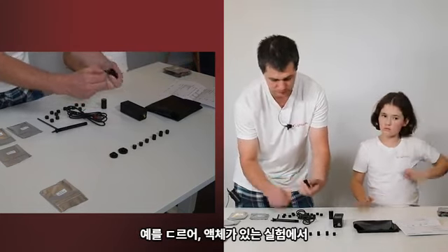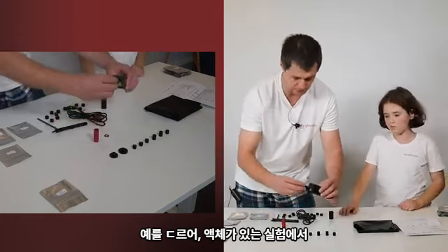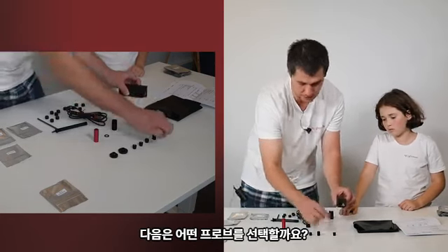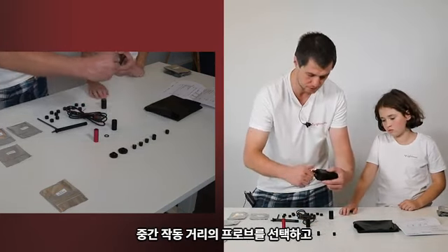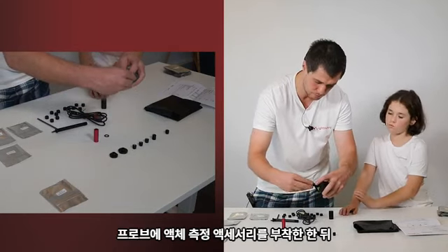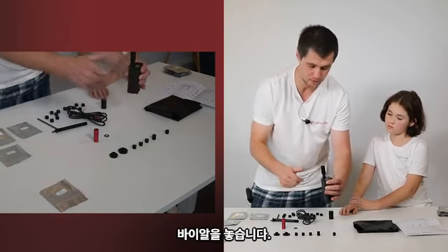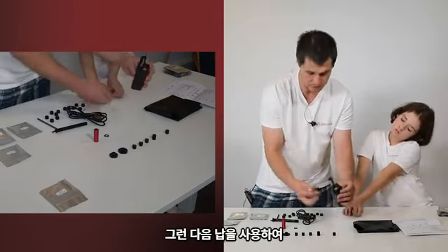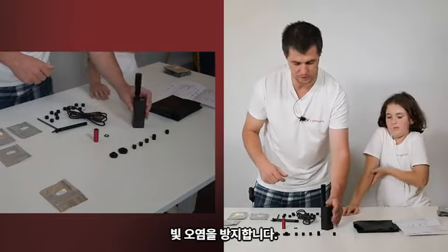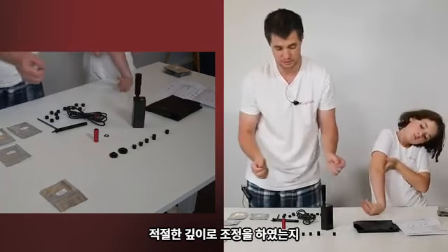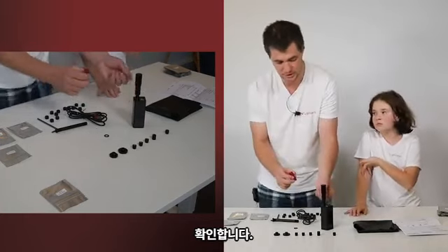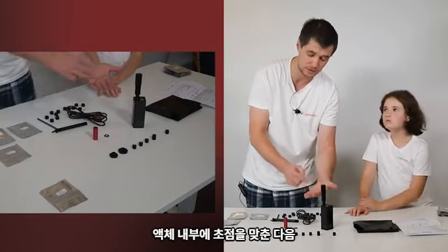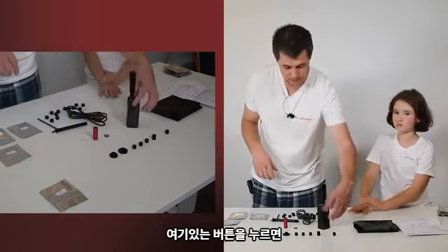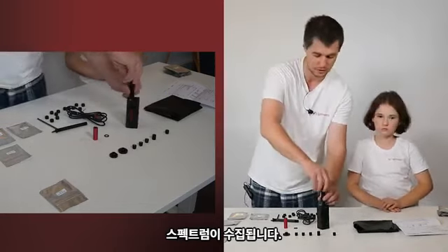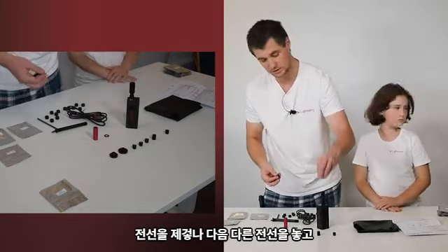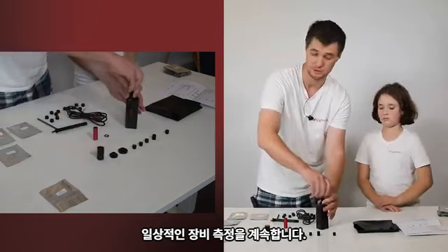For example, we have a vial where we have a liquid. Then the next thing we do, we select any probe, let's say middle working distance probe here, and we attach on a probe our liquid measurement accessory, and inside we place the vial, and then we use a lid to avoid any light contamination. And now the vial with the liquid is inside, and with this tool we adjusted the proper depth for the vial, so we don't measure the glass, we focus inside the liquid. And then we press the button here and we collect the spectrum. Then we open the cover, remove the vial, place another one, and continue routine liquid measurements.